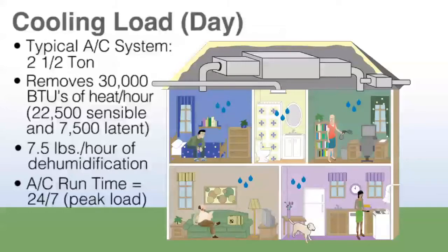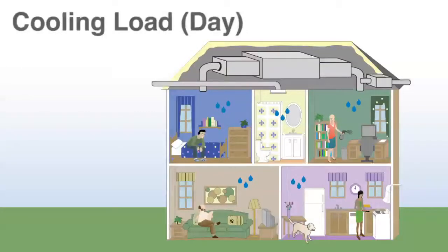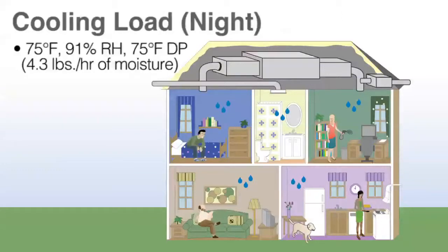Every day is followed by a night. On a warm day, we have a warm night — let's assume for the example we've got a 75 degree evening. We've got 91% relative humidity, which is a 75 degree dew point. As this 100 CFM of air enters the home, it represents 4.3 pounds of moisture per hour.